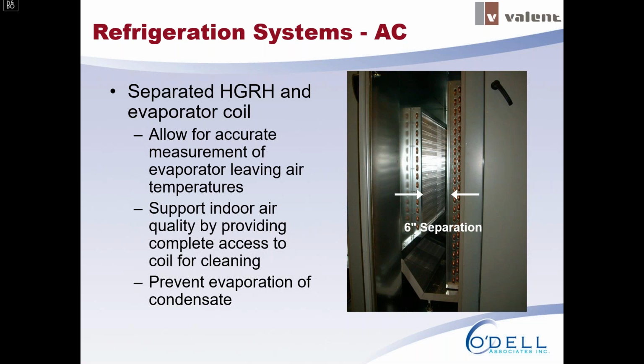The space also helps with maintenance, so you can get in between the coils and wash them off from time to time as needed. And the last advantage is you'll see there's a drain pan down at the bottom of the DX coil, and that gap allows the condensate to drain off the coil and out of the unit. If those two coils are mounted flush together, like some of our competitors do, then it's a lot harder for that condensate to drain off, and some of it can get evaporated back into the airstream because it hits the hot gas reheat coil, and that's really not what you want to have happen when your goal is to dehumidify. So, these are some of the design considerations that Valent looks at, and we're very intentional about designing our equipment to give you optimal design control when you're trying to control to a dry bulb temperature and a dew point temperature.